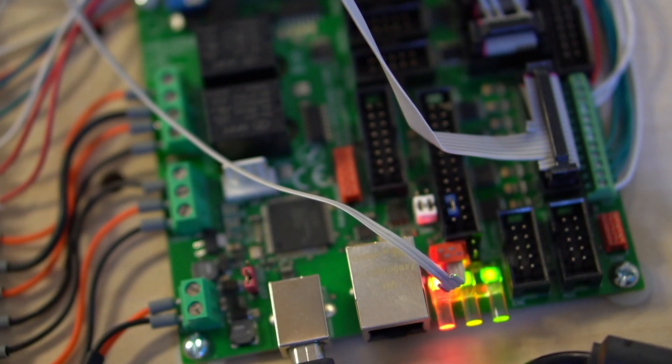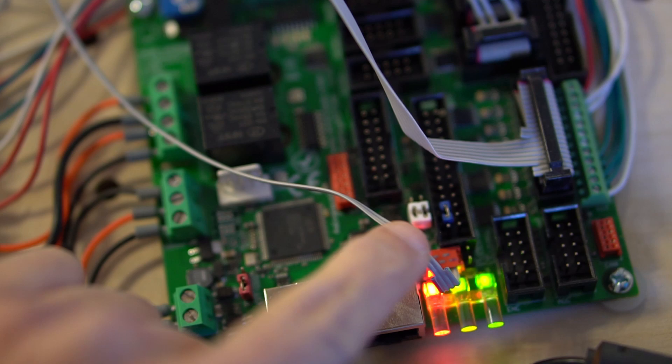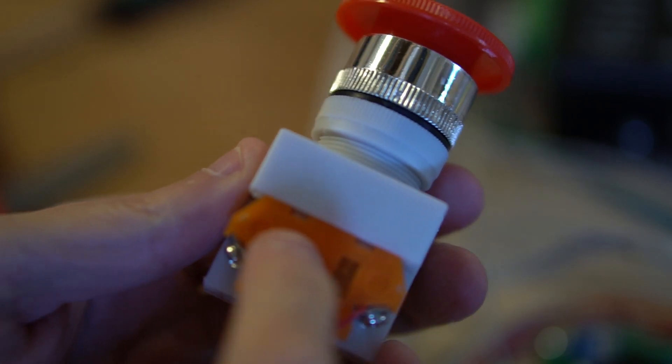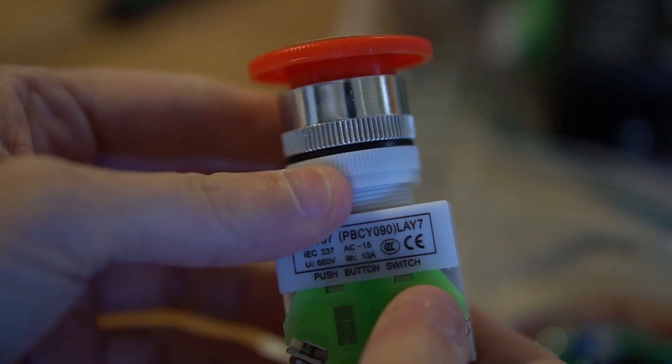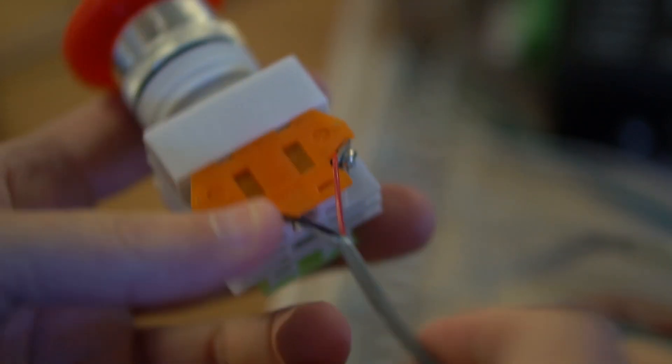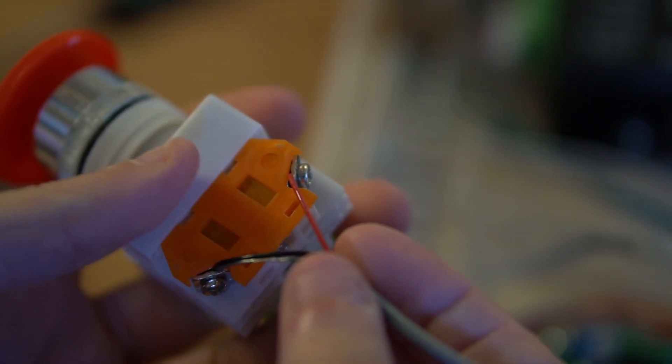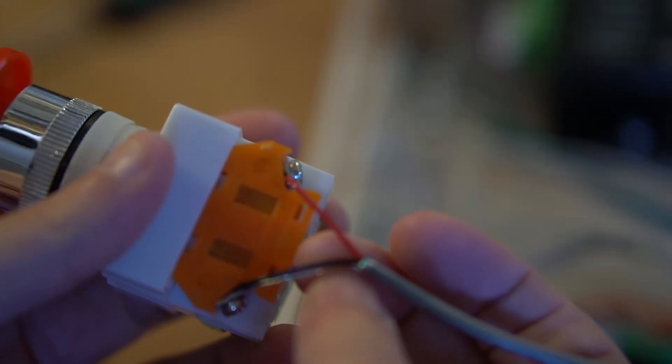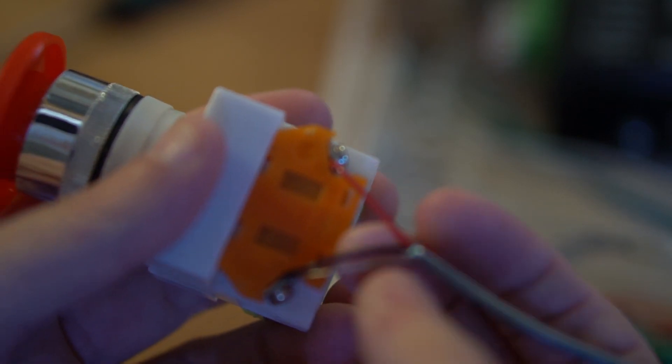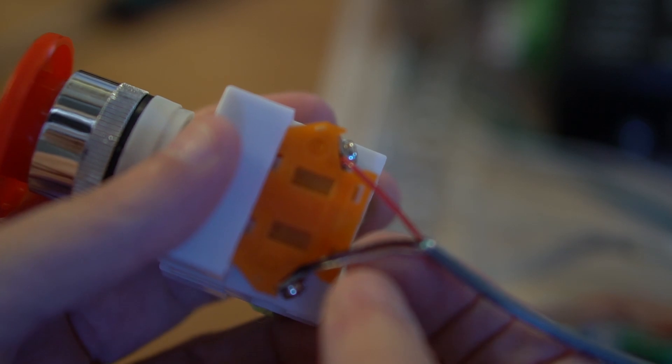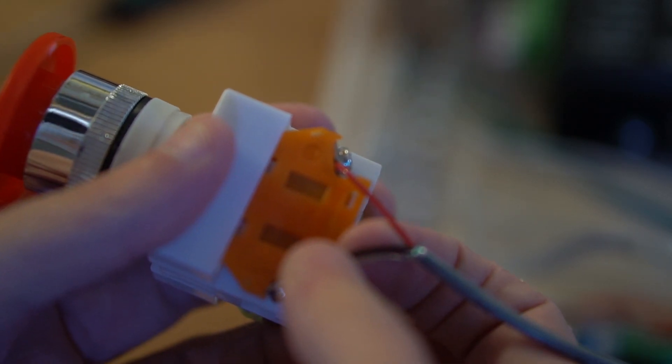I have the two conductors of the e-stop connector broken out to two terminals on a long terminal strip. I will use the normally closed side of the e-stop switch. The side is colored orange, the other side is bright green which is normally open. The cable that is used for this is a two conductor shielded cable to eliminate the possibility of noise coming into the signal. This cable has an exposed conductor that is in contact with the shield throughout the length of the cable. This electrical noise that is present on the shield of the cable is connected to the black wire which is connected to ground.